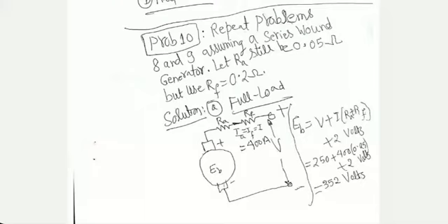Okay. So the load current is 400 amperes. Now, by the way, there is no difference between armature current, field current, and load current. They are all the same. That's a very important feature to remember in series connection. And the drop between EB and V now will be I multiplied by RA plus RF. And I'm taking brush drop also into account, which is 2 volt.